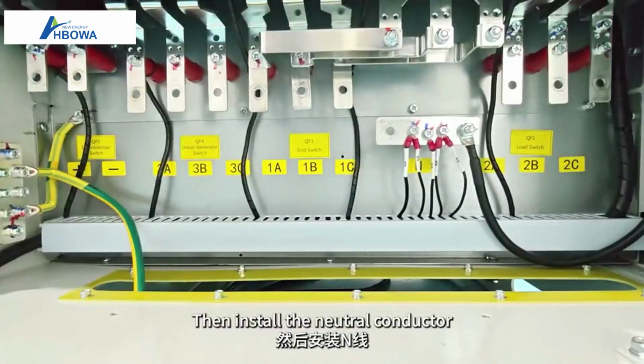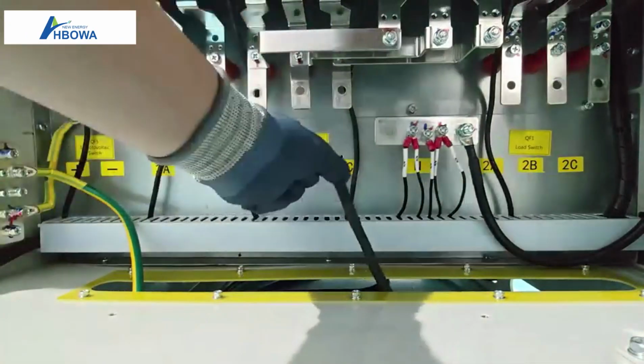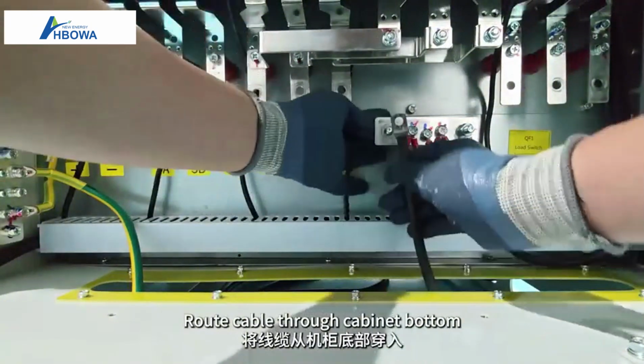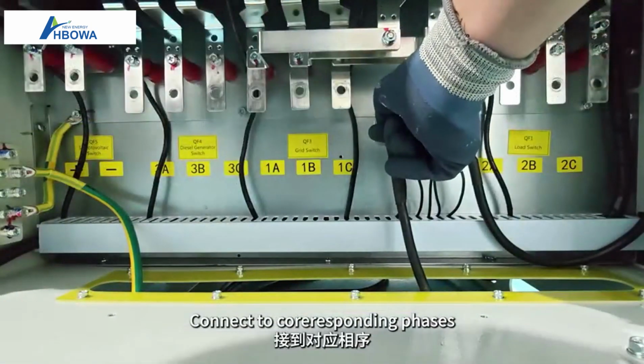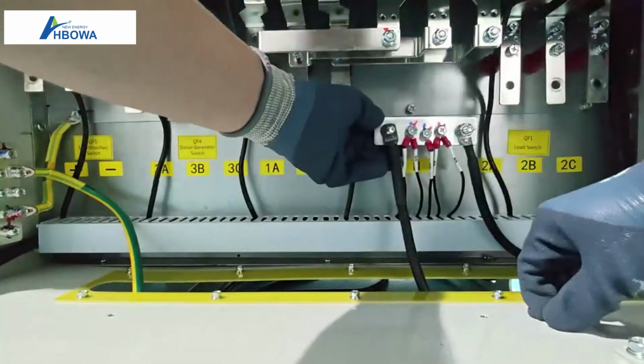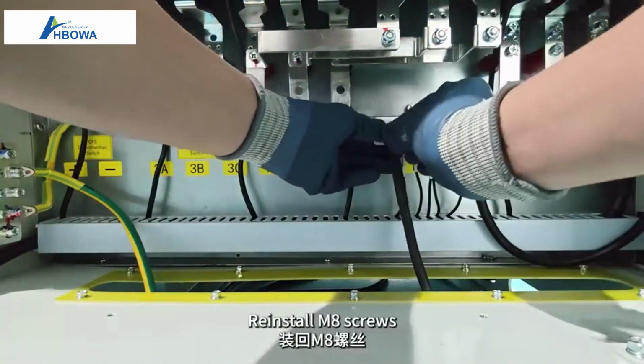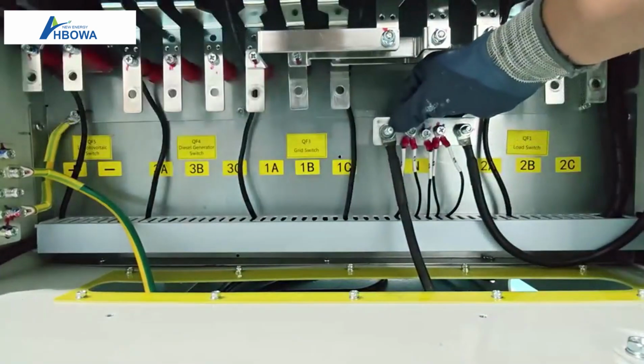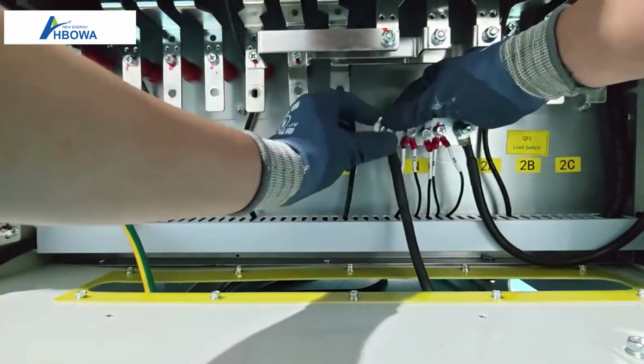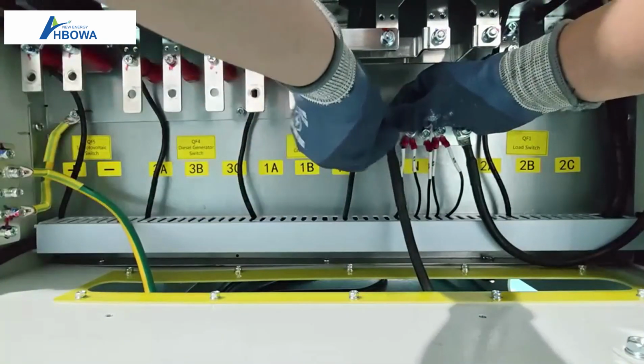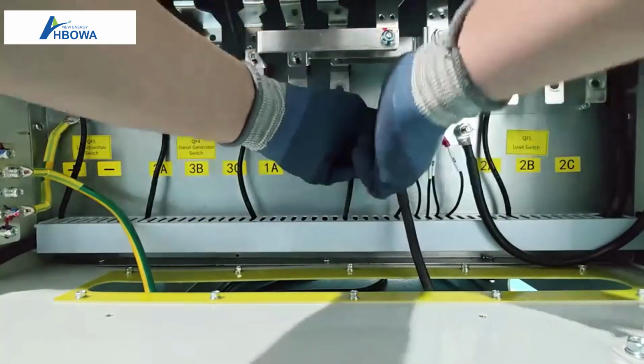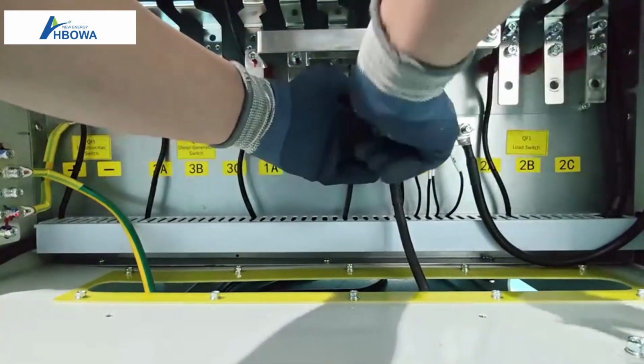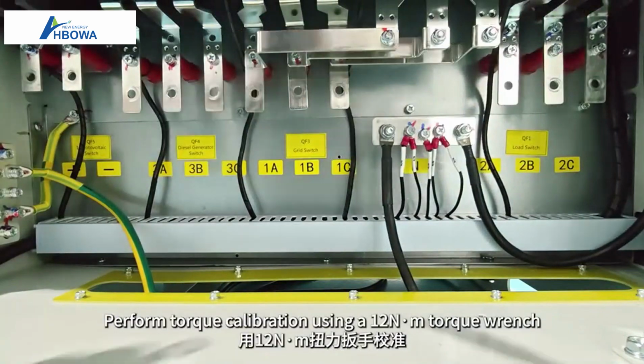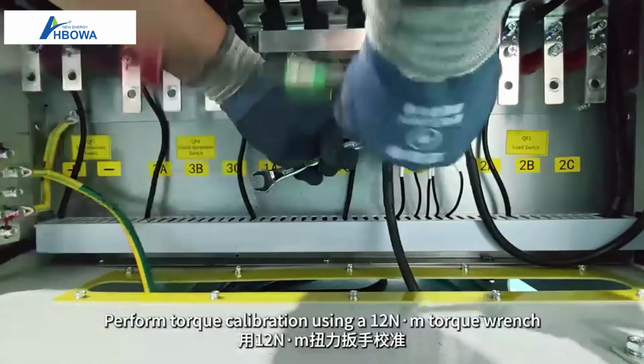Then install the neutral conductor. Route cable through cabinet bottom. Connect to corresponding phases. Reinstall M8 screws. Perform torque calibration using a 12 Nm torque wrench.